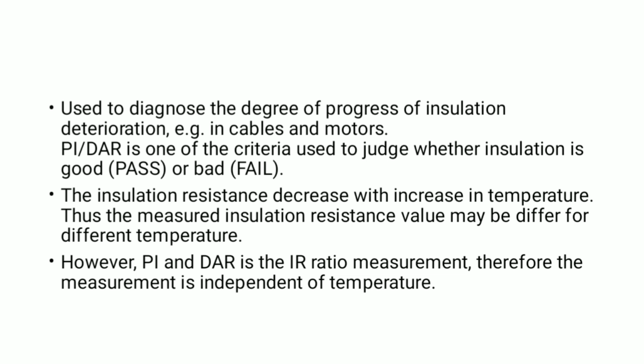Now the question may arise in your mind: if we are taking the insulation resistance test, then why is there a need for DAR and PI? Insulation resistance is always affected by various factors like temperature, moisture, dust. If your temperature increases, your insulation resistance decreases.